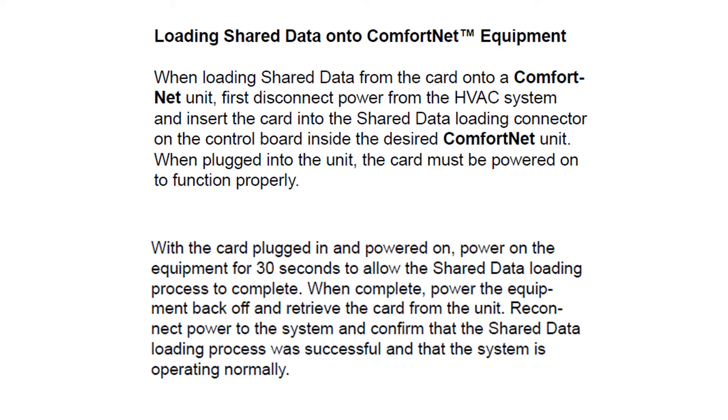Loading shared data on the ComfortNet equipment. We have another good video on this. If you are going to load the data, keep in mind you should power it down, plug it into the board, power it up. The equipment needs to be powered for a minimum of 30 seconds. The shared data will be loading on the board. When completed, power the equipment back off. You can retrieve the card from the unit, reconnect power and power up, and you should be good to go.